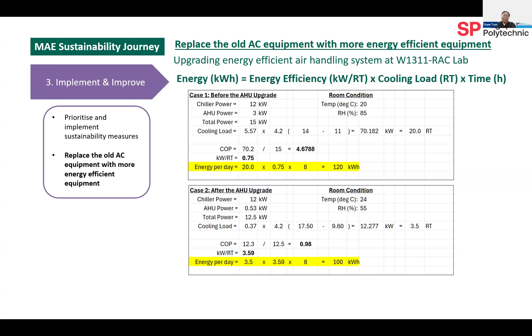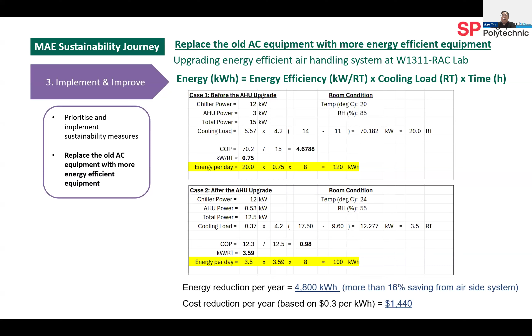This reinforces an important point here. When evaluating the energy consumption of AC systems, we must consider not only equipment efficiency, but also cooling load. By applying the right control strategies, we successfully reduced the cooling load from 20 RT to 3.5 RT here. This resulted in a substantial drop in energy consumption of about 20 kilowatt hours per day, achieving over 60 to 70% energy saving from the airside alone. In summary, the airside system upgrade has resulted in over 16% of energy saving.